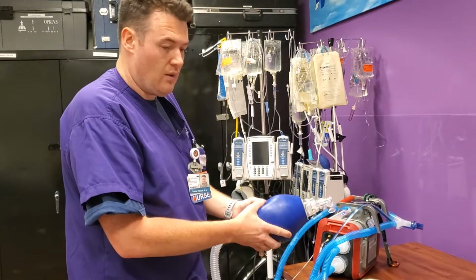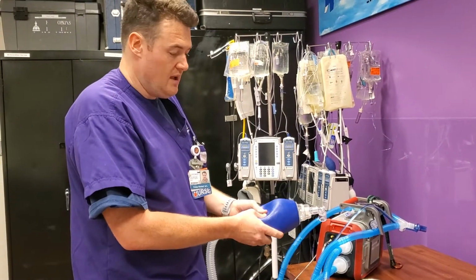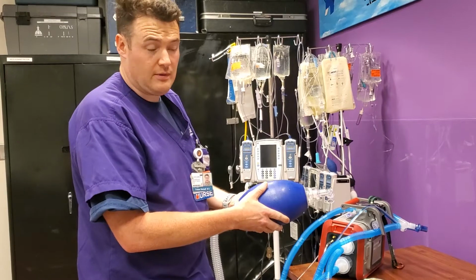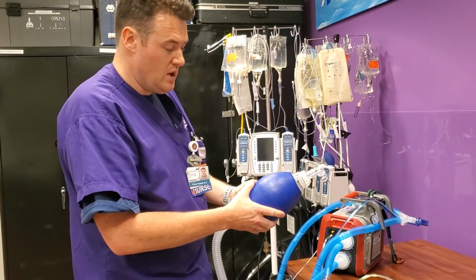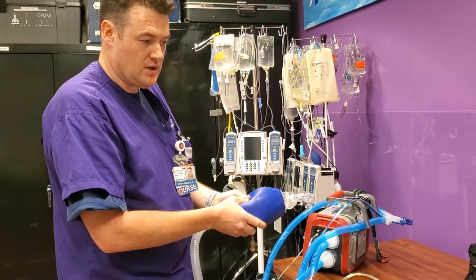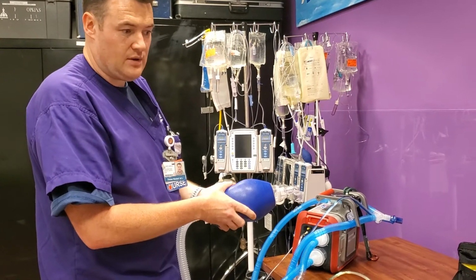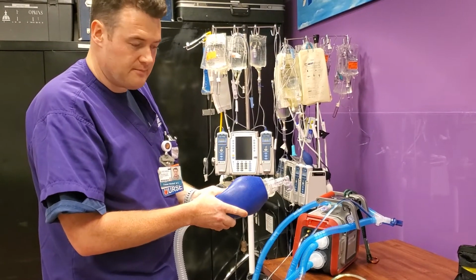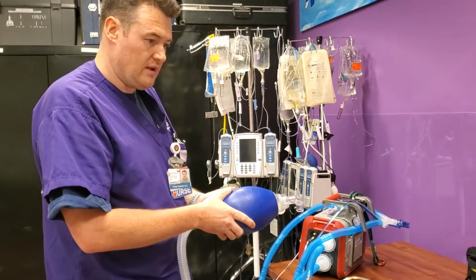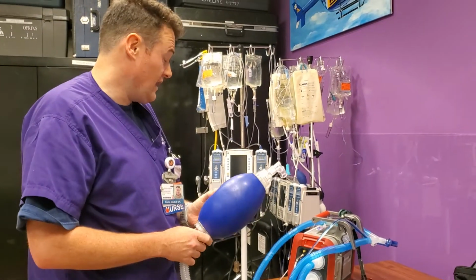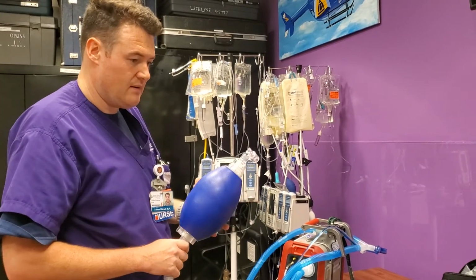Obviously, as recommended with our last one that we used to use, the iNO Max, you always want to keep continually bagging the patient. If we leave it latent for too long, we can have a buildup of nitrogen dioxide, which we don't want. So we're just going to be continually bagging the patient until we can get to the closest facility, or we figure out what was wrong with our ventilator. I think that covers the majority of our NoxBox. If obviously there's any questions, you can reach out to myself or Chad, and we should be able to answer them.